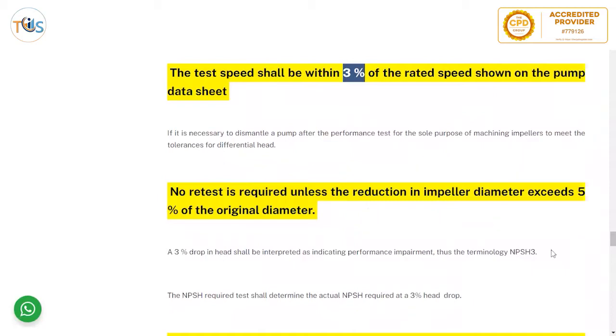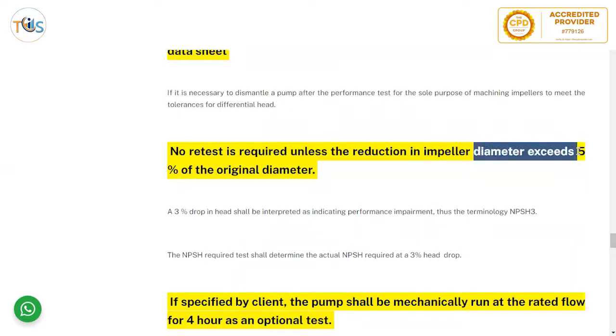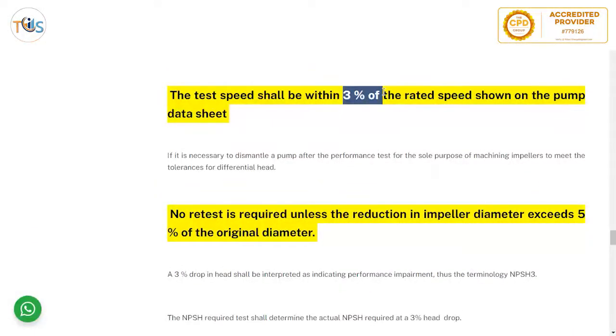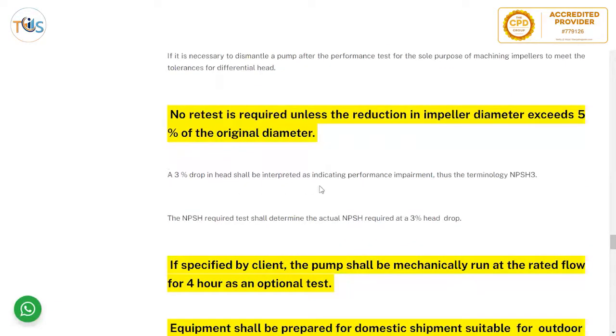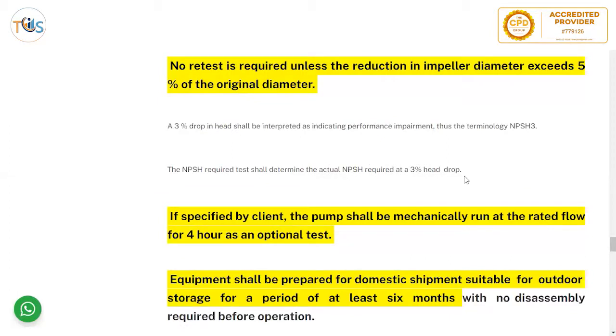If it is necessary to dismantle a pump after the performance test solely for the purpose of machining impellers to meet differential head tolerances, no retest is required unless the reduction in impeller diameter exceeds 5 percent. A 3 percent drop in head shall be interpreted as indicating performance impairment. This is called NPSH3 — net positive suction head required — and up to a 3 percent drop is accepted.